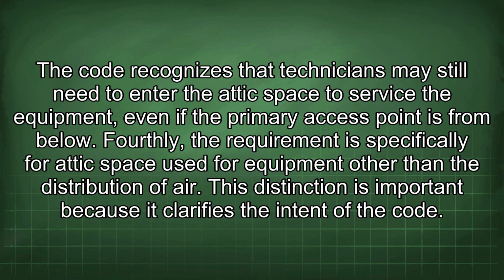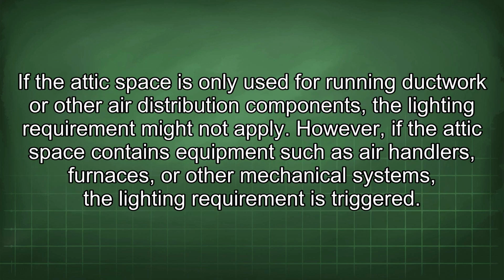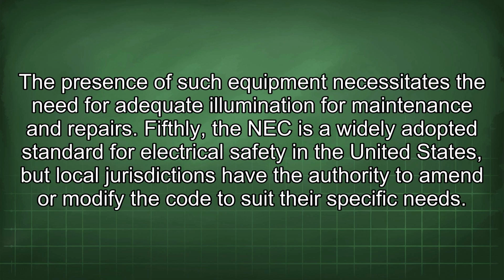Fourthly, the requirement is specifically for attic space used for equipment other than the distribution of air. This distinction is important because it clarifies the intent of the code. If the attic space is only used for running ductwork or other air distribution components, the lighting requirement might not apply. However, if the attic space contains equipment such as air handlers, furnaces, or other mechanical systems, the lighting requirement is triggered. The presence of such equipment necessitates the need for adequate illumination for maintenance and repairs.